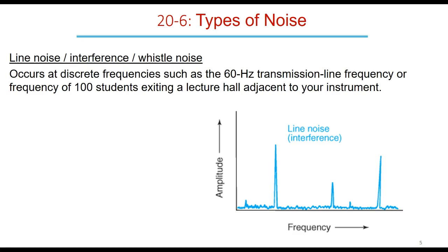That's because the NMR is that sensitive that we need to separate it from other instruments that are, quote, noisy, especially our mass spec instruments that have to run under vacuums pumps, which are really, really noisy. We've also got things like sonicating probes, which can be super, super loud and have really outrageous frequencies. You wouldn't want the instrument to pick up that.